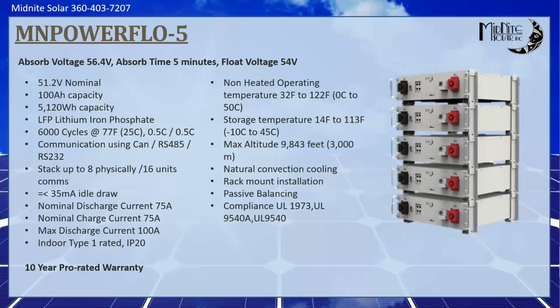So that's what the closed loop really does, it gives you that control of the inverter from the battery. The inverter no longer has to try to measure the battery voltage through its own terminals and do all the absorb time and all that. The battery takes 100% care of that. And like I said, that communications for closed loop is Pylon protocol. So we do have a CAN bus document, I believe, that we can share if somebody needs it for some reason. But yeah, any common inverter out there today will communicate with these batteries using that protocol.